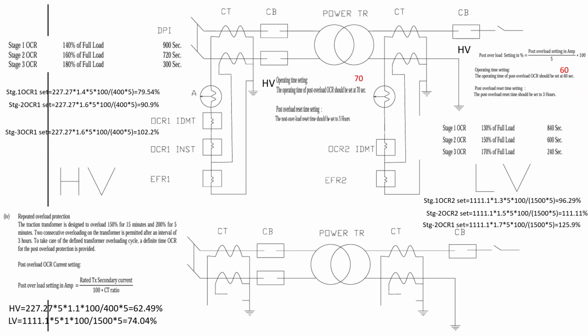So the same thing will follow in the LV side also, but the percentage of stage 1, stage 2, stage 3 is reduced by 10%. Instead of 140%, it is 130%. Then stage 2 is 150%, and stage 3 is 170%. And for the post overload also, in the same manner, it has taken 100%. Already you have seen the post overload setting in the LV side, and its timing is also given. For the HV side it is set at 70 seconds, and in the LV side it is set at 60 seconds, and after 3 hours another overload it can withstand.